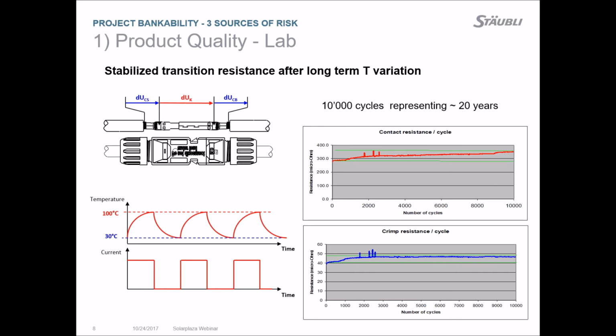Data on long-term performance can really help indicate the real quality. Here is an example of an internal beyond-the-norm test, 10,000 cycles, representing around 20 years of our product, showing a stable contact resistance. Additionally to the resistance of the contact parts, there is also a resistance of the crimping, the connection of the contact parts to the cable.